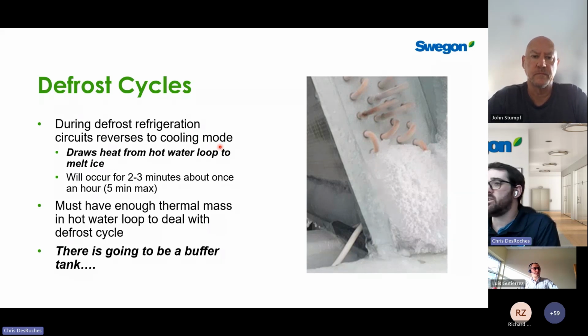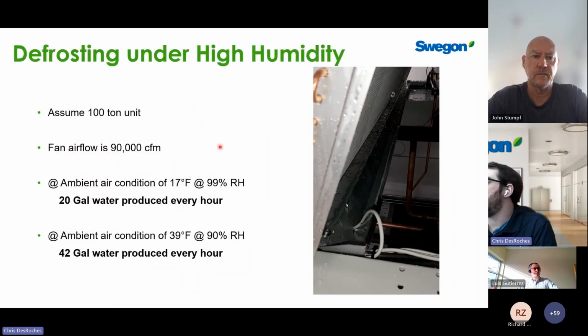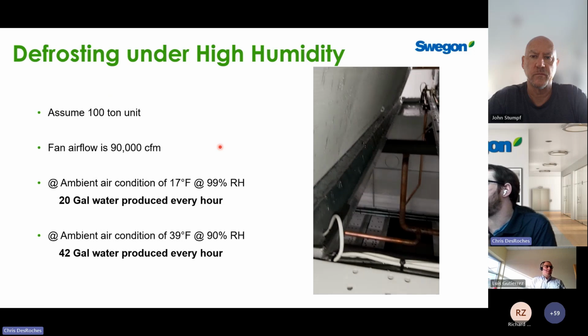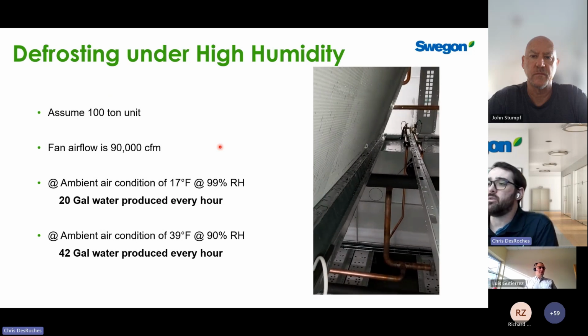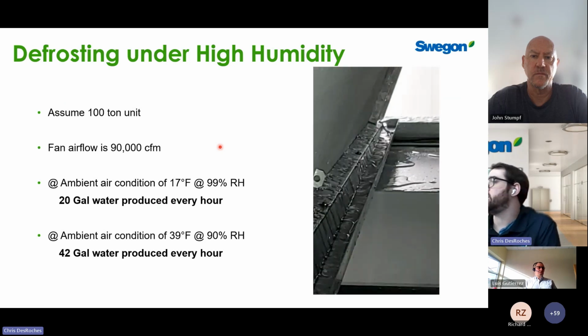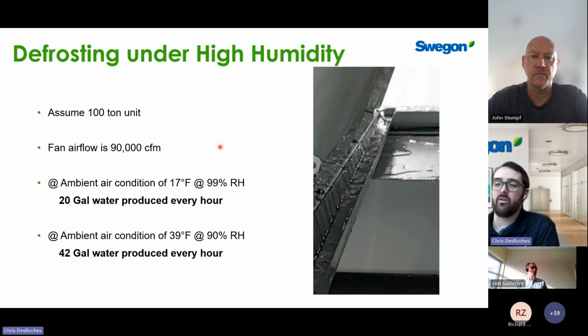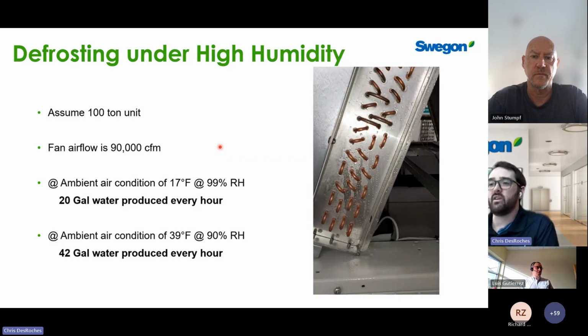So buffer tank's going to come into play for this that we'll talk about in a few slides, but purely on the condensate level, this is an image of condensation happening as part of a defrost cycle. But the example in the math that we worked out in terms of figuring out how much water is generated, a 100-ton nominal heat pump will have between 90 and 100,000 CFM going across the coil. And it's really humidity that's driving the frost and ice buildup. So when we have really cold conditions and 99% RH at 17 F, we might still produce about 20 gallons of water every time that we defrost. But really the condition that will cause frosting the most is actually when it's warmer at a high humidity, because we can carry more moisture in the air at warmer temperatures. So at 39 Fahrenheit ambient with 90% RH, every hour when we defrost, we could be generating 42 gallons of water when that machine defrosts.